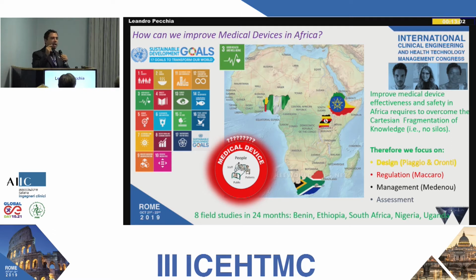Because you design an oxygen concentrator thinking you will have pure air in the surgical theater, 99.9%, so your device expects this air. If you enter a surgical theater in Africa, well not all, but many, especially in rural countries, they do not have any air filtering. So now this device, which the manufacturer suggests changing the filter after 2,000 hours of working, should actually be changed after 10 hours, or the truth is they should not be designed like that.